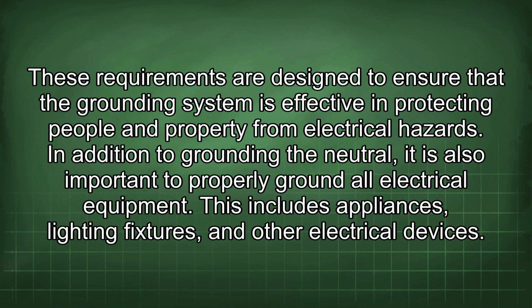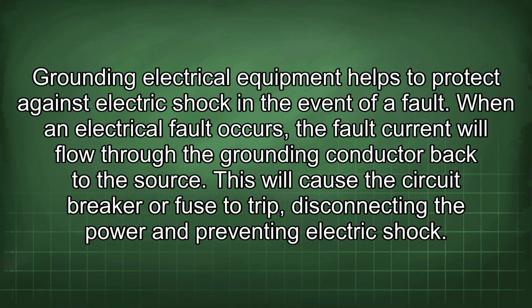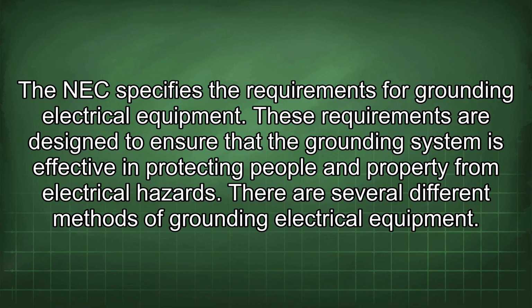In addition to grounding the neutral, it is also important to properly ground all electrical equipment. This includes appliances, lighting fixtures, and other electrical devices. Grounding electrical equipment helps to protect against electric shock in the event of a fault. When an electrical fault occurs, the fault current will flow through the grounding conductor back to the source. This will cause the circuit breaker or fuse to trip, disconnecting the power and preventing electric shock. The NEC specifies the requirements for grounding electrical equipment. These requirements are designed to ensure that the grounding system is effective in protecting people and property from electrical hazards.